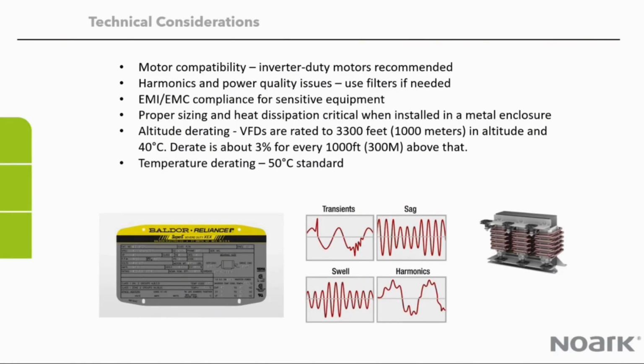When determining your application, you should take into consideration the compatibility of the motors, any potential power quality issues, harmonics, and any sensitive equipment that would be affected. Of course, heating, and one thing I didn't cover was the altitude. The drives are rated specifically to 3,300 feet, 1,000 meters in altitude. And if you're operating above that, then you would need to derate. The same would be the case if you're operating in a hotter environment.